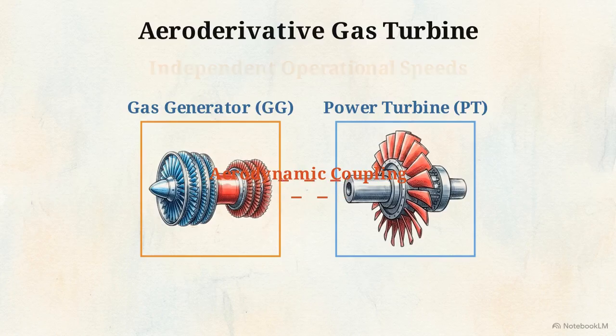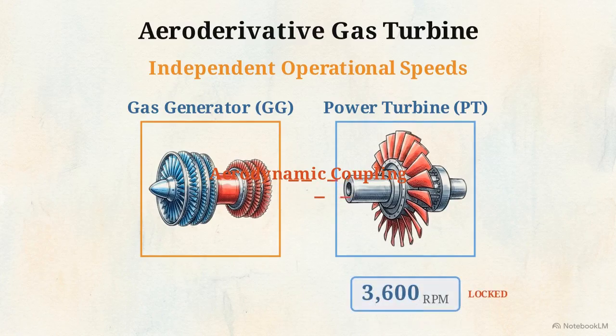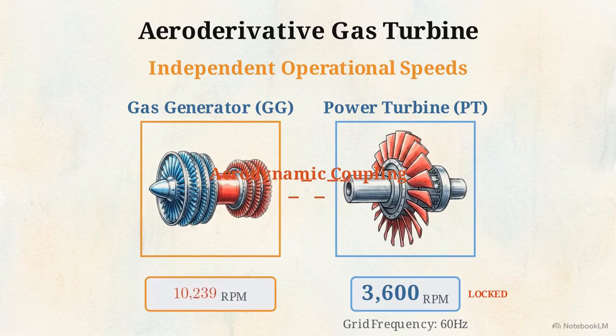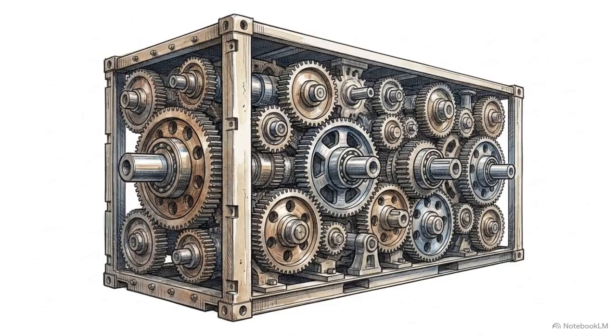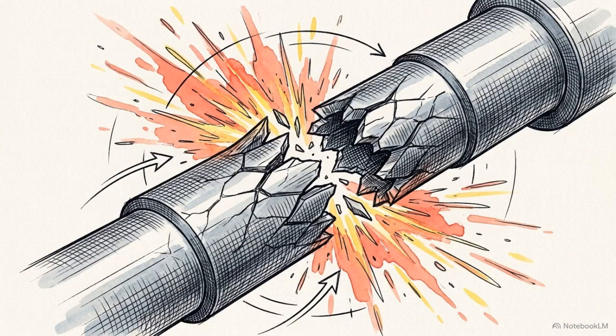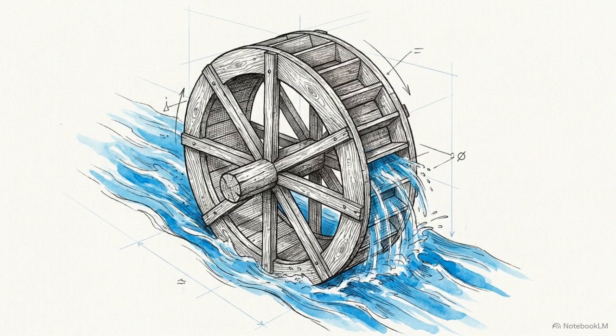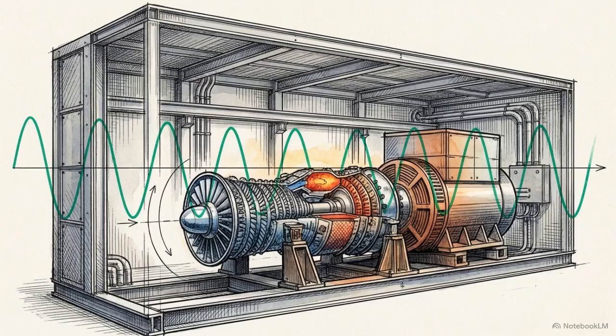This separation allows for a critical operational advantage. The power turbine can stay locked at a rock-steady 3,600 RPM to match the electrical grid frequency, while the gas generator core fluctuates up and down past 10,000 RPM to meet changing power demands. A single shaft design would require a massive, complex speed-reducing gearbox to force the core's high-speed rotation down to the generator's synchronous limit. By transferring power through gas rather than metal, the engine maintains perfect electrical synchronicity without exposing its internal components to the mechanical stress of variable speed coupling.